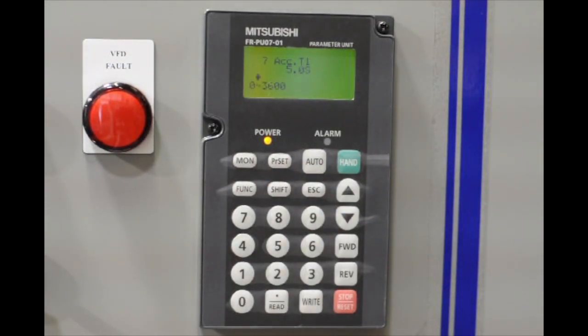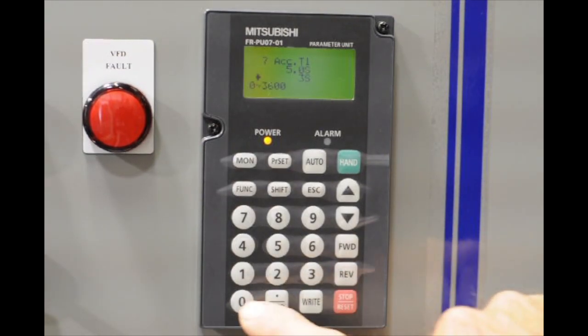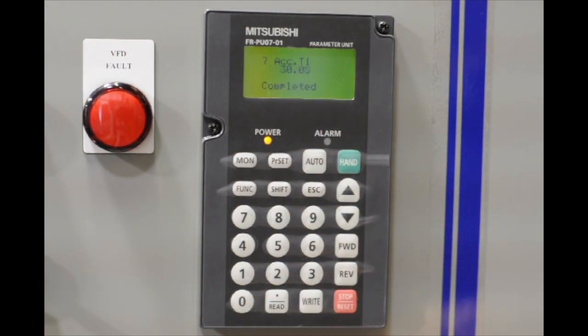Parameter seven is our accel time. The drive comes standard with five seconds, but typically, we like to put in something around 30 seconds if the equipment allows. So we're going to go ahead and type in 30, and hit write.